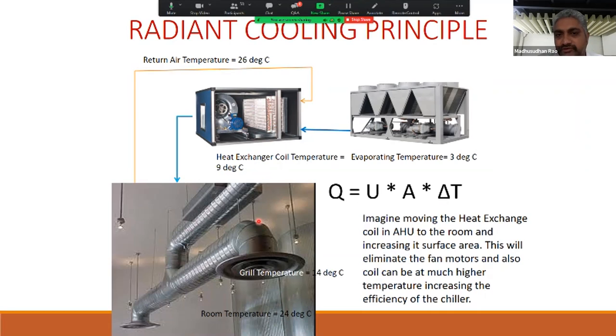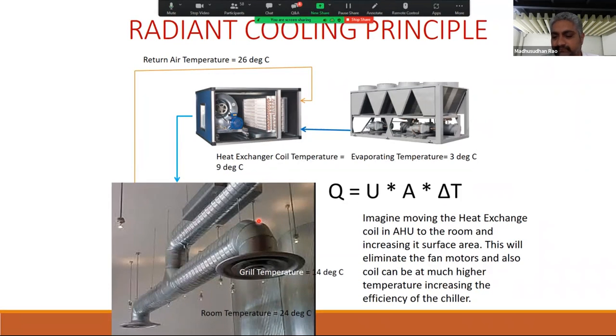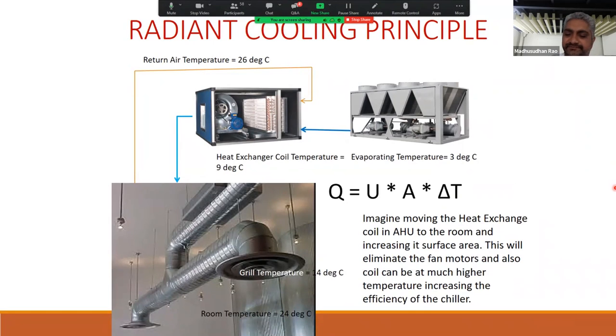Okay, because per square meter of the heat exchanger, we will get less output now because we are not doing dense heat exchange. But since we have increased the surface area, the absolute amount of heat exchange remains the same. Okay. So that would be a simple way to understand how we are doing this. We are essentially moving the heat exchange from the AHU room into the space itself.